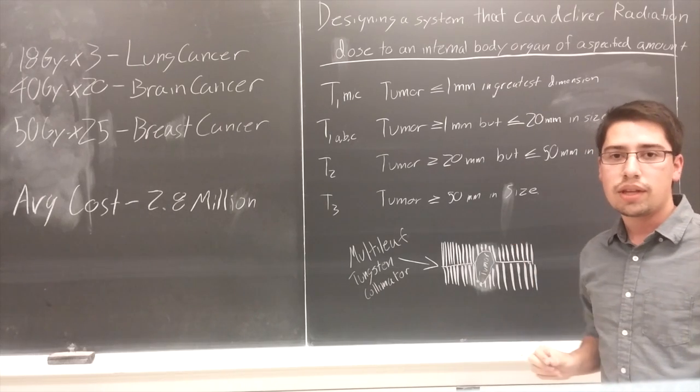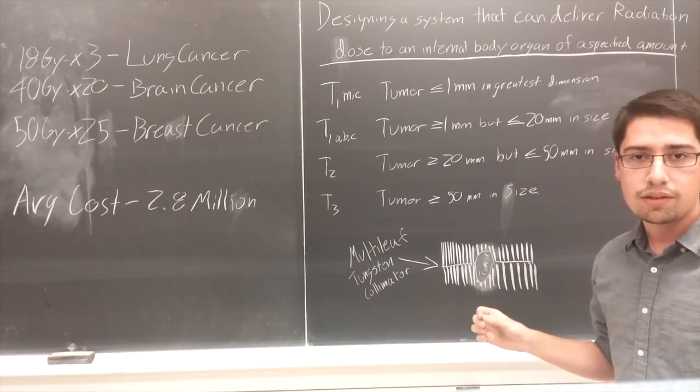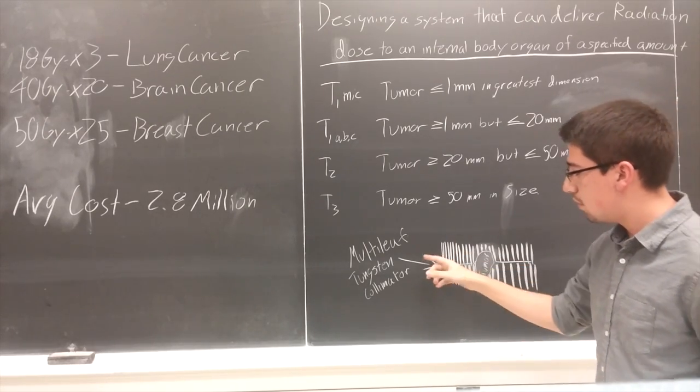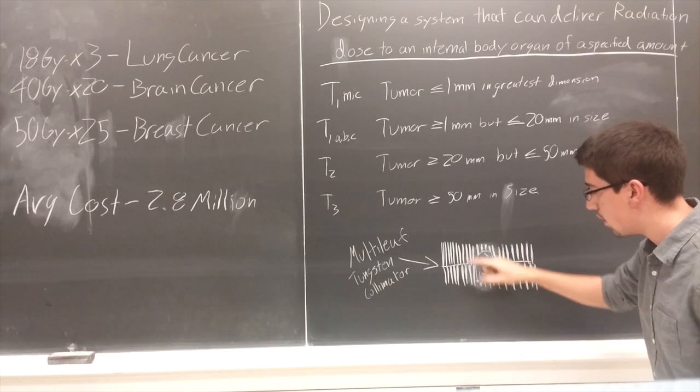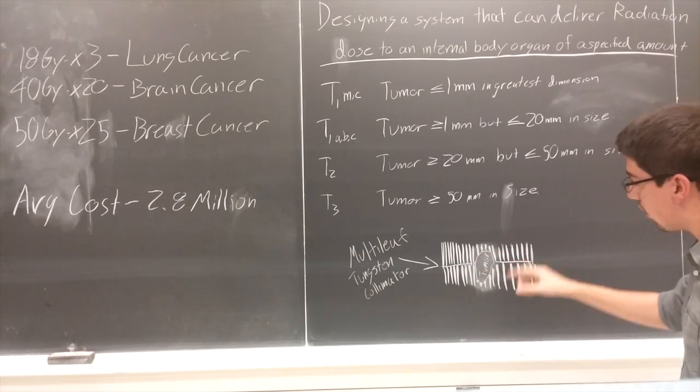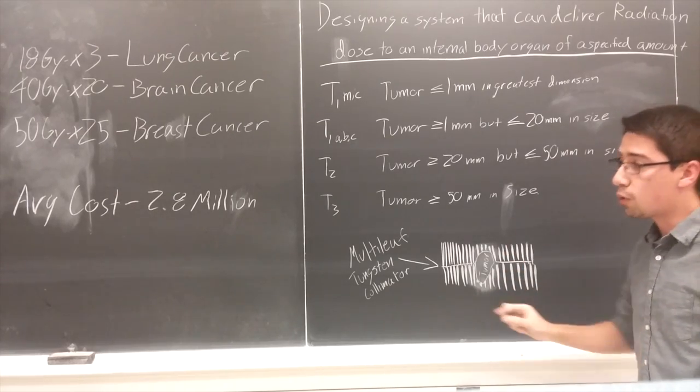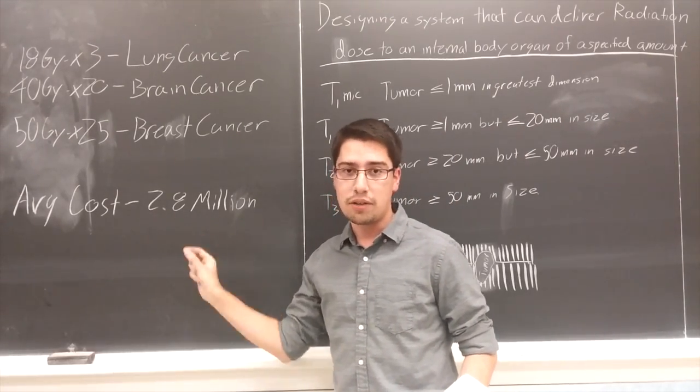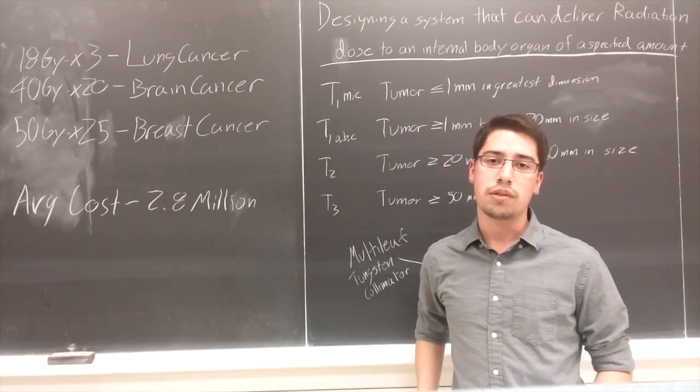And another very important thing is the shape of the tumor, which is why our specific linear accelerator has multi-leaf tungsten collimators at the very end to adjust to the size using all these tungsten sheets right here, to adjust to the size and the shape of that tumor. Of course, the cost comes up to 2.8 million, but I don't think that's because of the tungsten. That's because of the design, which we will go into next.